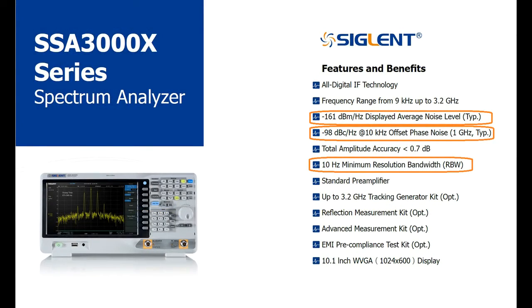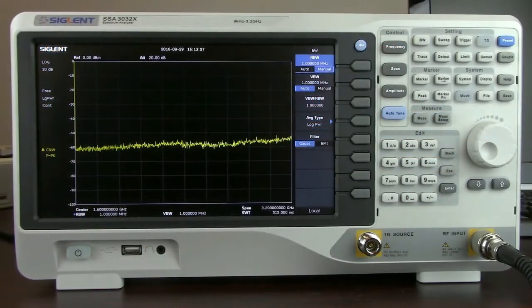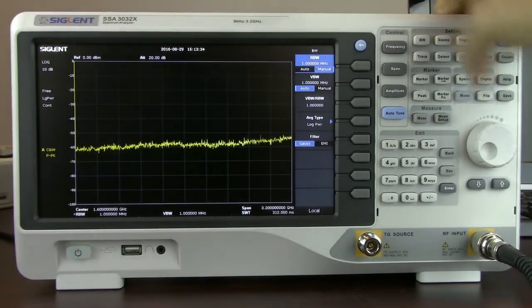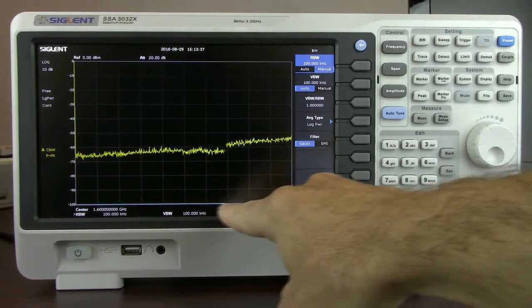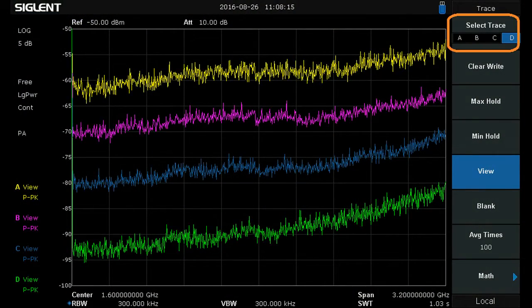The SSA 3000X also features a 10 inch WVGA display and it does measure a full 10.1 inches with about 7 inches of actual trace area. When you slow down the resolution bandwidth and the sweep you'll see there's a progress bar that helps indicate exactly where you are located in the frequency space. The instrument also features the ability to show up to four traces simultaneously.